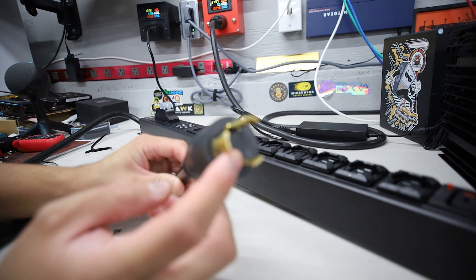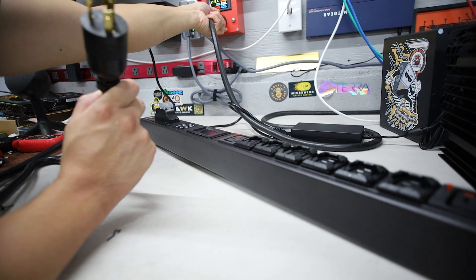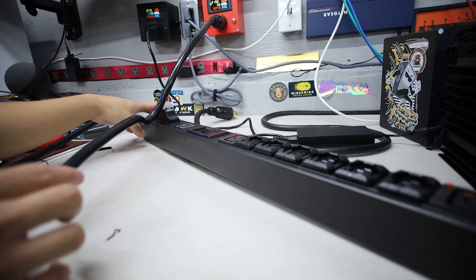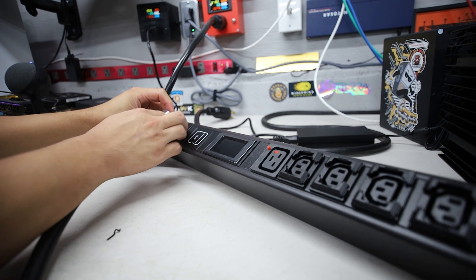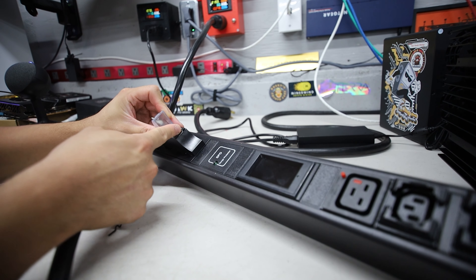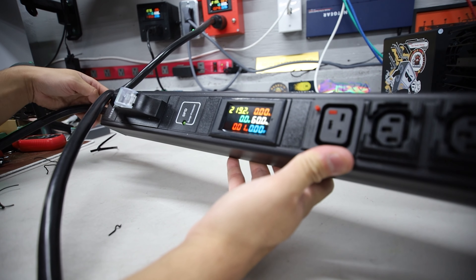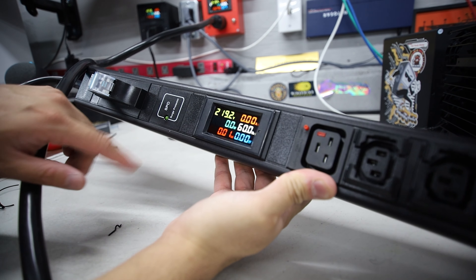They have the surge protector here, as well as the 30 amp big boy breaker, which is really cool. It's a 240 volt capable PDU. The voltage rating is 100 to 250 volt, and most people are plugging this in for 220 or 240 volt. So this will go up to 7,200 watts on a 240 volt 30 amp circuit. But in terms of the 80% safety rule, you probably want to go up to 5,760 watts.